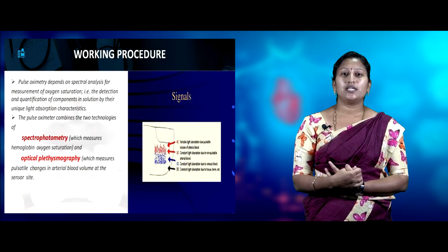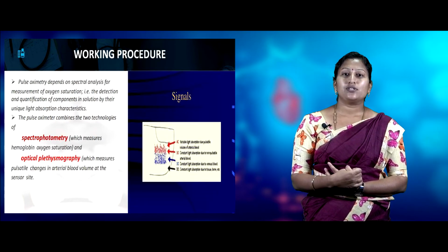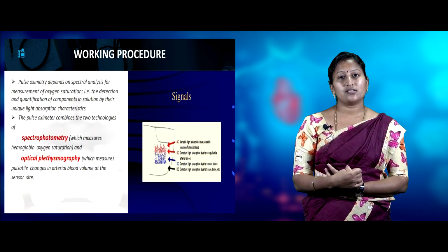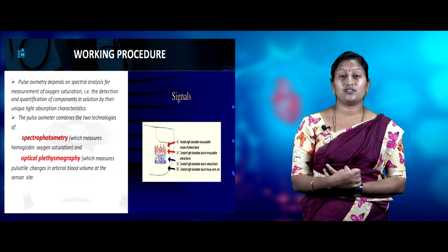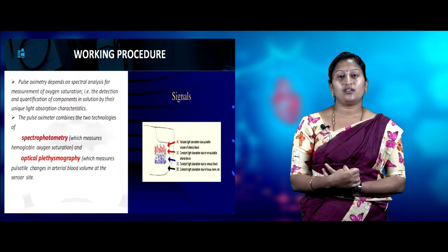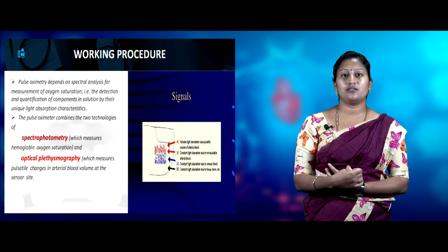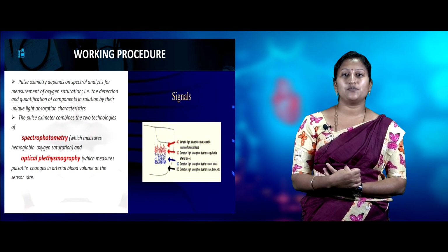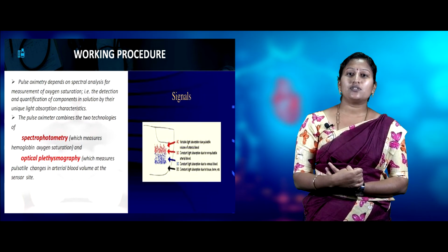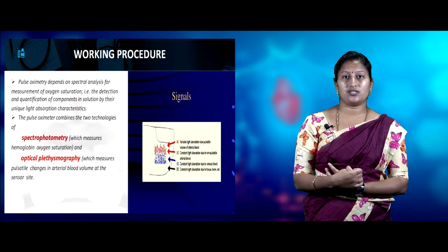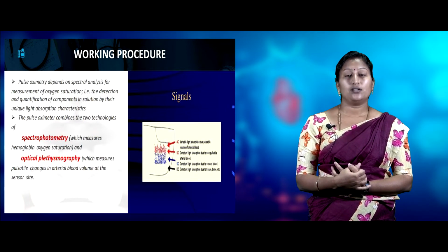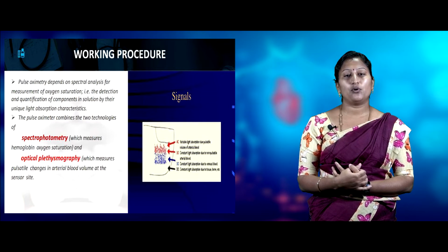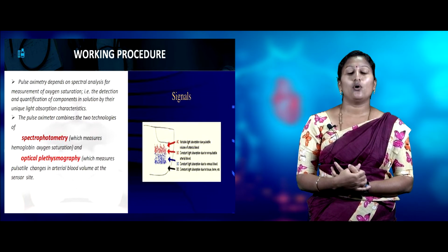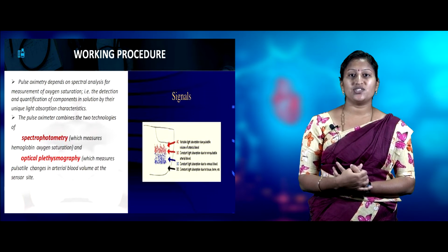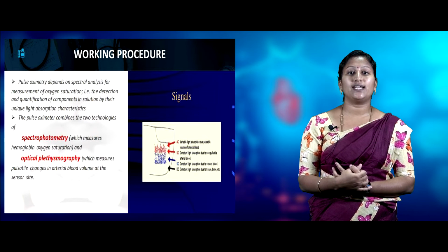Now let's see the working procedure of a pulse oximeter. The pulse oximeter depends on spectral analysis for the measurement of oxygen saturation, that is the detection and quantification of a component in a solution by its specific light absorption characteristics. The pulse oximeter combines two technologies, that is spectrophotometry, through which it measures the hemoglobin oxygen saturation, and optical plethysmography, through which it measures the pulsatile changes in the arterial blood volume at the sensor site.